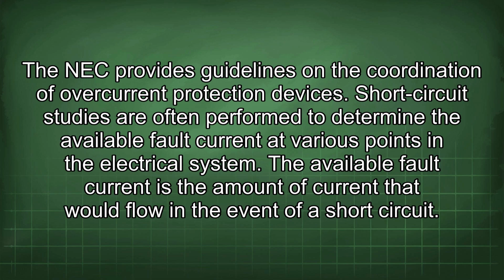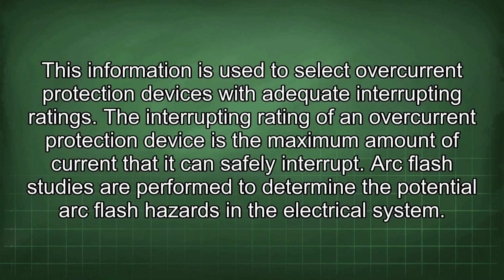Short circuit studies are often performed to determine the available fault current at various points in the electrical system. The available fault current is the amount of current that would flow in the event of a short circuit. This information is used to select overcurrent protection devices with adequate interrupting ratings. The interrupting rating of an overcurrent protection device is the maximum amount of current that it can safely interrupt.